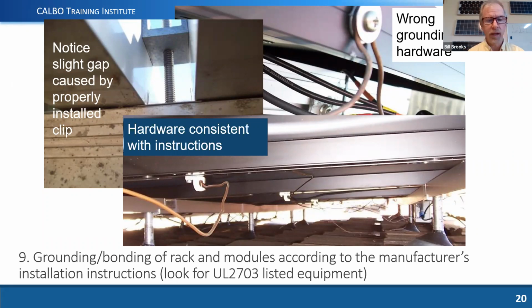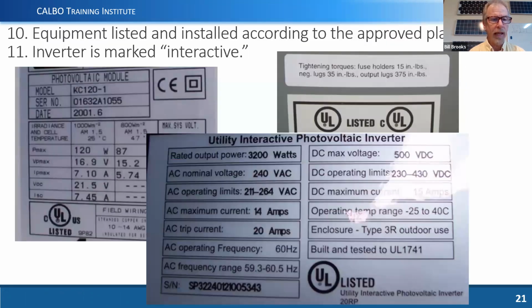Because to do it right without the UL 2703 listing is very labor intensive and difficult. And this would be an example of a labor intensive and difficult install. One of the reasons that I was such a strong supporter of UL 2703 is that trying to install a number 6 bare copper conductor underneath an array and trying to turn the modules over was an absolute nightmare and just not a very effective way to do it anyway. So grounding clips or clamps that actually create the bonding necessary for the module frames and the rails is the way you want to go. And hopefully most people have been doing that for the last 4 or 5 years.